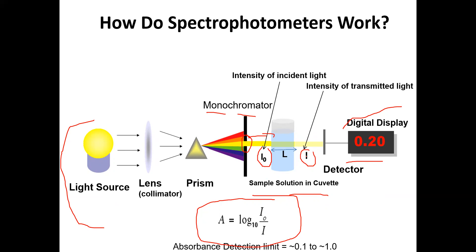L indicates the path of the light from one side of the cuvette to the other — usually one centimeter. The detection limit of this machine based on this formula is between 0.1 and 1; it's only accurate between these values. If the absorbance is more than 1, it will not be accurate and the sample must be diluted to bring it below 1.